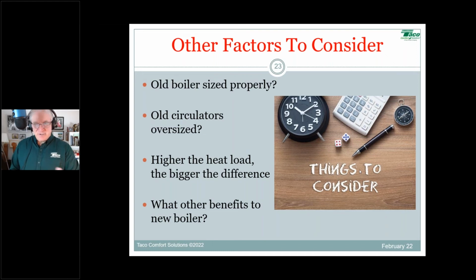They give you a really cool free book with every ModCon boiler you buy, and in it there are charts that help you figure out the flow and head that boiler circulator needs. It's remarkable how small those pumps need to be. That's a great way to enhance the efficiency of the system, don't oversize that boiler pump, and properly size your system pump. A Delta T pump is a great way to go about that.